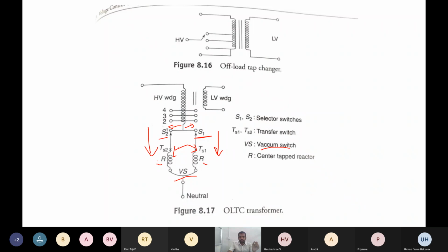So this is our transfer switch 1 and this is our transfer switch 2. So at the time of changing the position from S1 to S2, for example, at that time the TS1 should be opened. And the current that is flowing in the reactor should be one half of that current that is flowing through the TS1. So you must have measured the current. Only when one half of the current is flowing should you be ready to change the position.